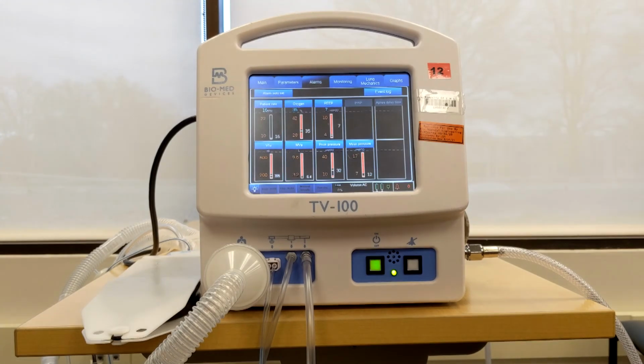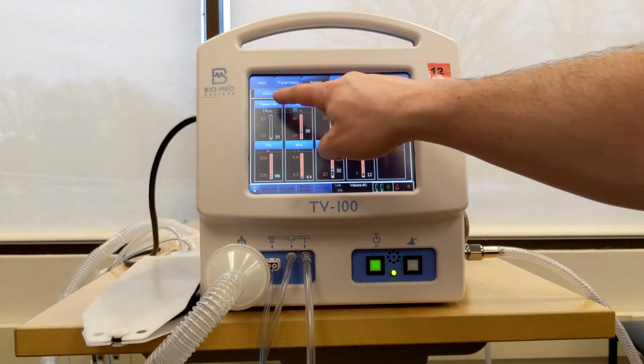The Alarm Auto Set button is located at the top of the Alarms page. The Alarm Auto Set button is only available during ventilation. During standby mode, the Alarm Auto Set button will be inactive and will be displayed in gray. The Alarm Auto Set button is only available when the TV-100 achieves set parameters and the breathing pattern is determined to be stable. The TV-100 determines the breathing pattern is stable by detecting if there are no large changes in pressure or volume levels over a period of delivered breaths.